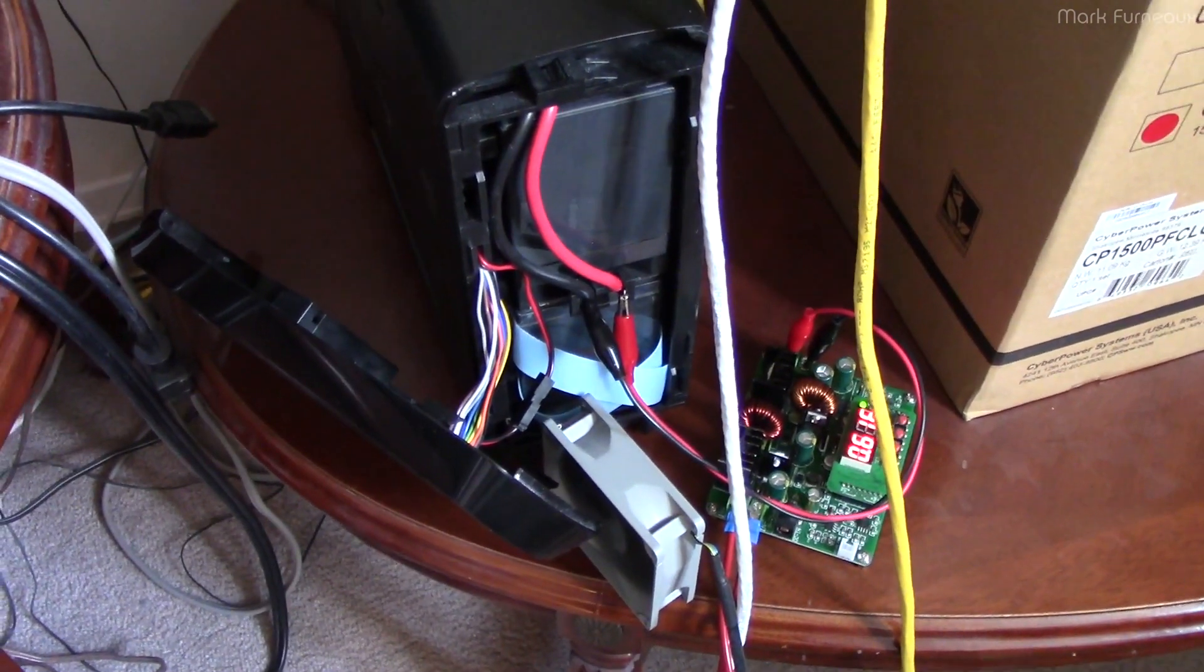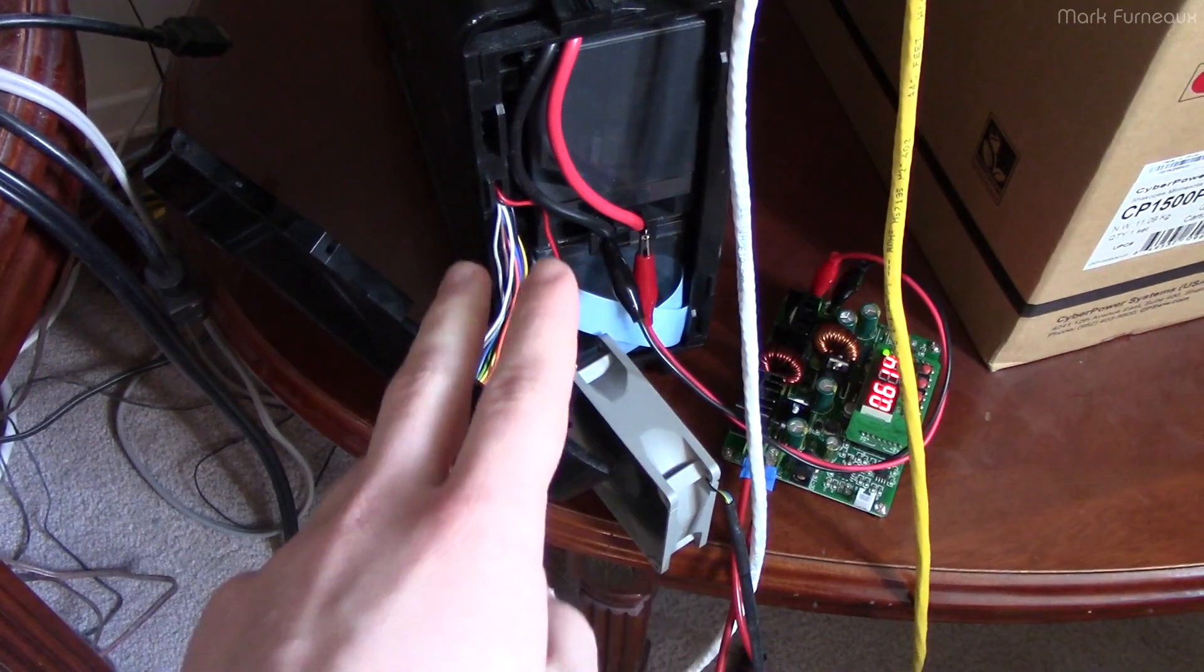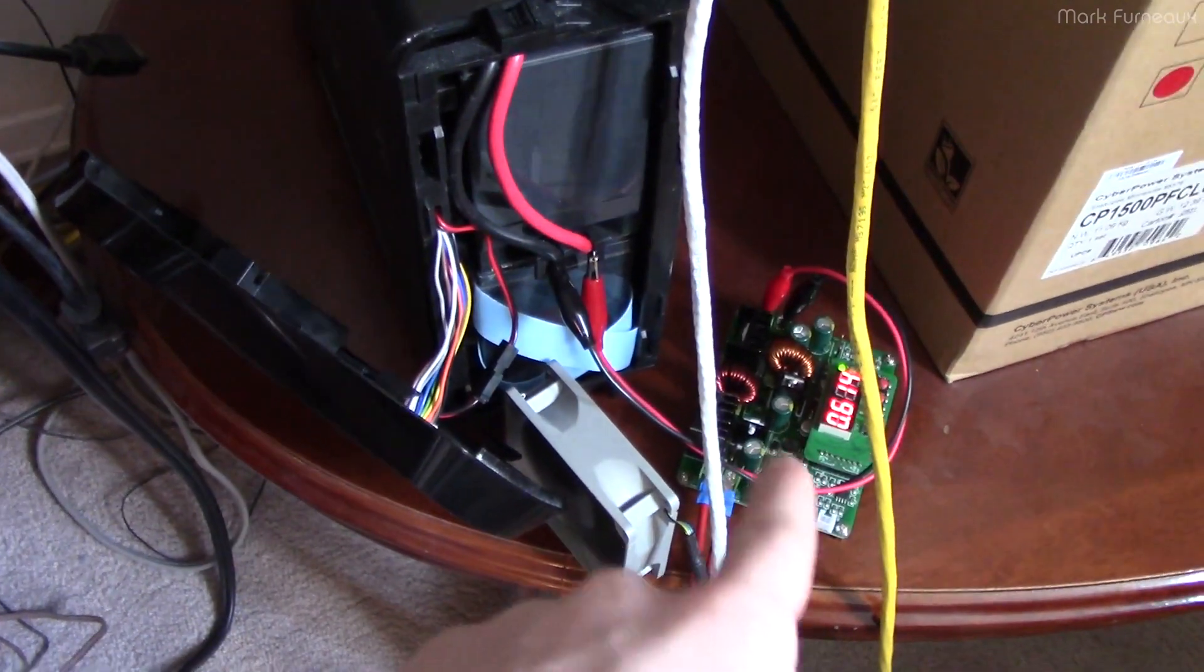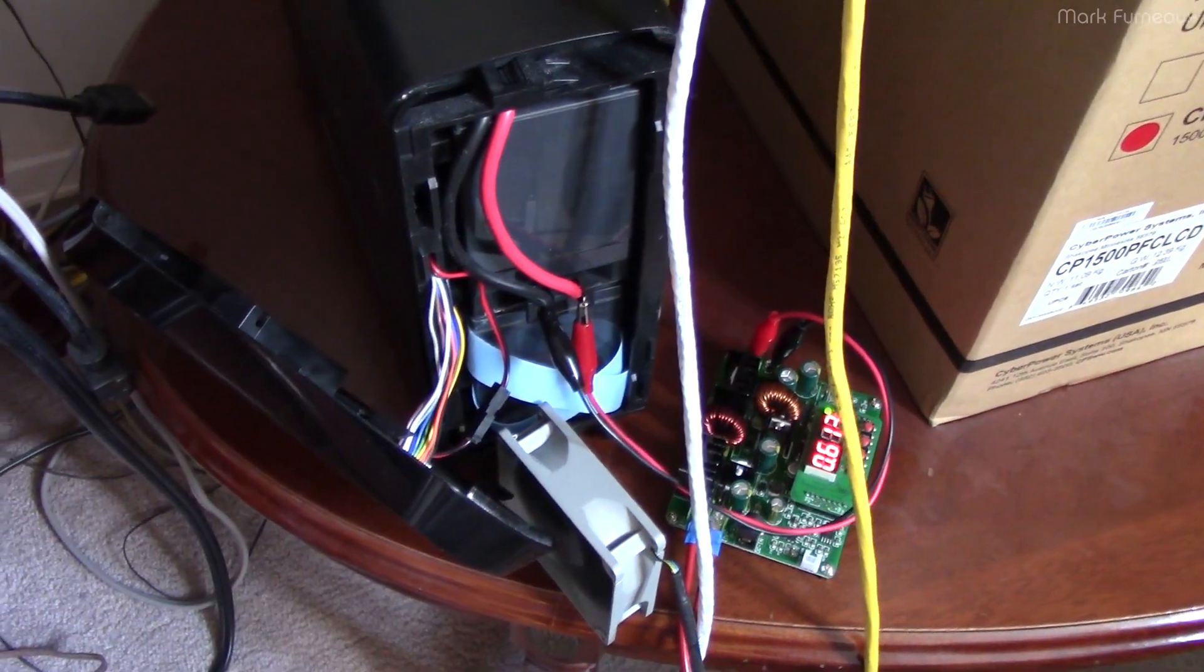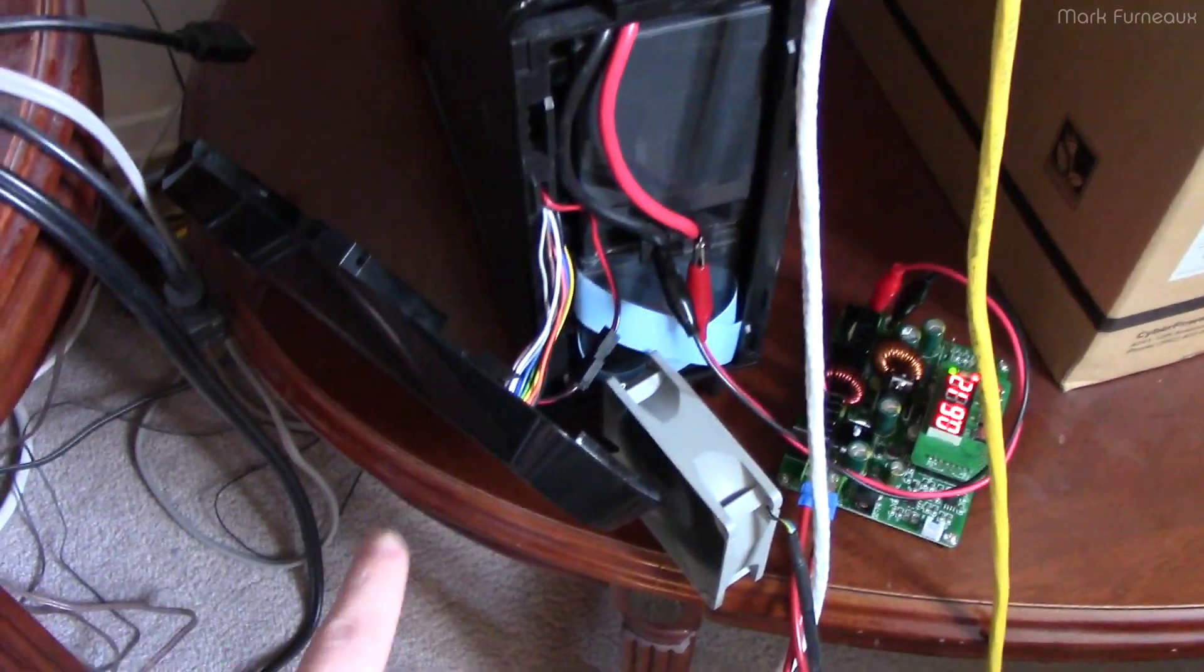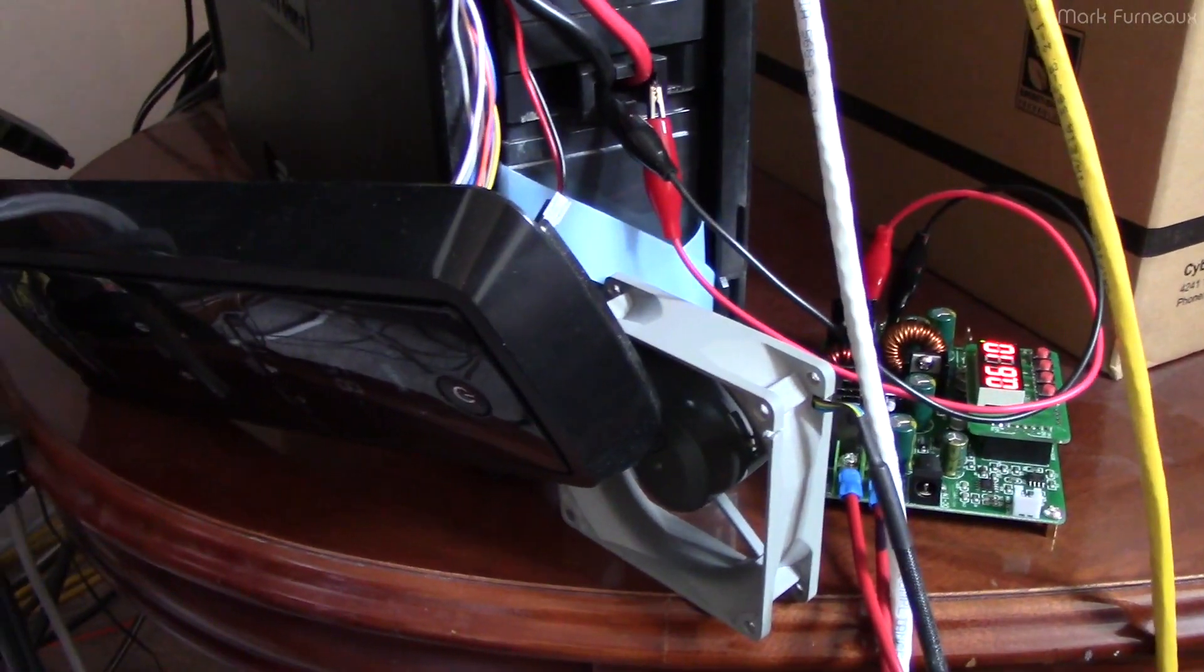And now it's actually gone from constant current to constant voltage, so we're actually at the equalization charge voltage of these two, which is 28.8, and so the current is what you're seeing there. It's dropping as we complete the charge. But the data, as far as the charge percentage goes, is exactly identical to what it looks like without this adding in any charge.